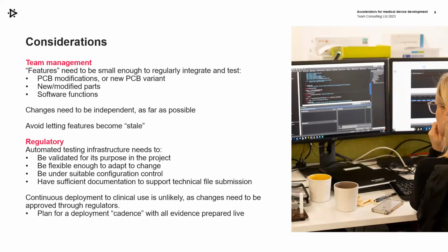Finally, as a point of consideration, continuous deployment, which is the next step beyond continuous integration, that's unlikely to happen in a medical setting. We have to go through regulators. Our deployment can't happen as soon as a feature is integrated, unlike in, say, consumer software world. What we can do is plan for a deployment cadence.